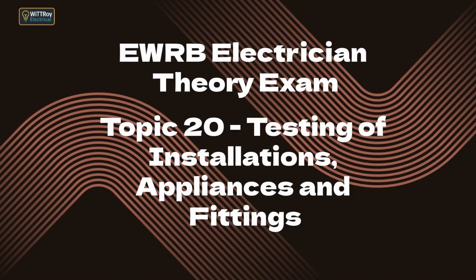Topic 20I. Explain the methods by which fittings can be either disconnected from the circuit under test or shorted out to prevent damage from the test voltages. To protect sensitive equipment during insulation testing, electricians can disconnect the fitting completely, remove lamps, control modules or drivers, isolate the circuit at a terminal block, short active and neutral together and test between and to earth, or test the wiring before connecting any equipment. This prevents damage to electronics.